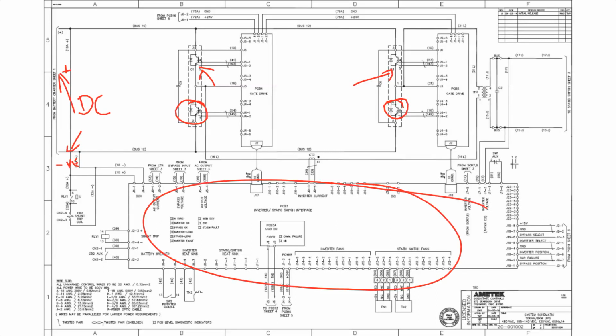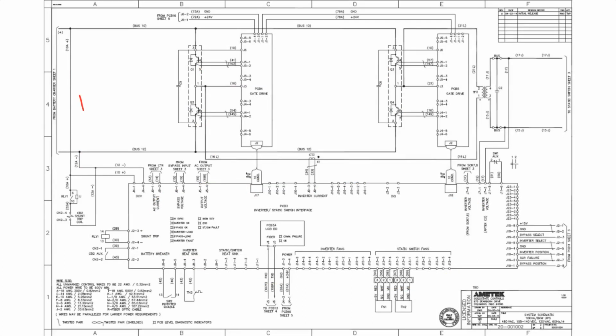So we have this inverter static switch control board. It sends the signals to these IGBTs and tells them when to switch on and off. But in the grand scheme of things, it's quite simple to remember. We have DC on this side, and then it goes through this transformer, and we have a beautiful synthesized AC sine wave that is filtered and has very low THD, total harmonic distortion. It's just a very, very clean sine wave that your load circuits can rely on. So in the block, that's all you've just got to remember in this drawing here. We've got DC on this side, AC on this side.